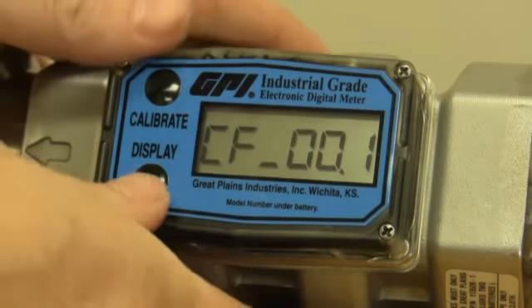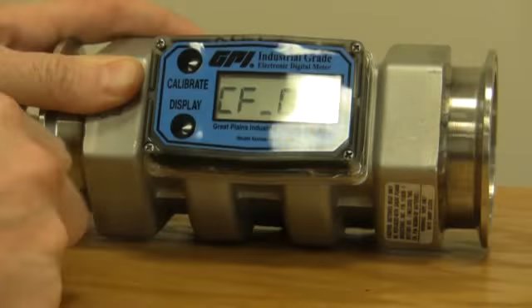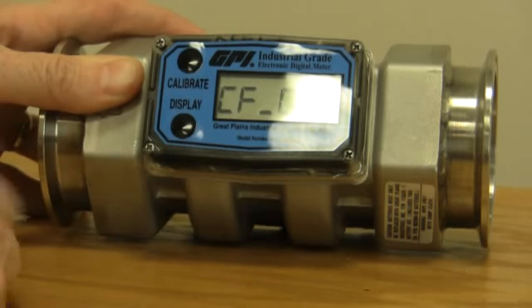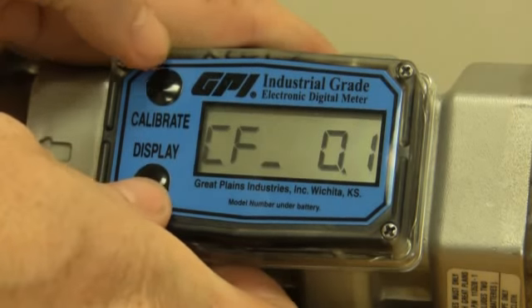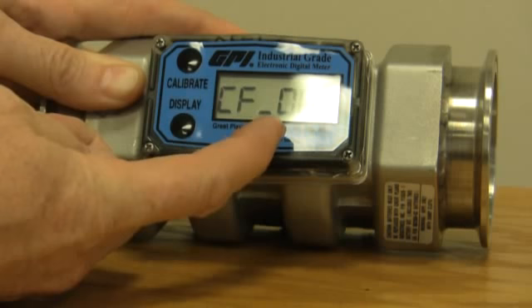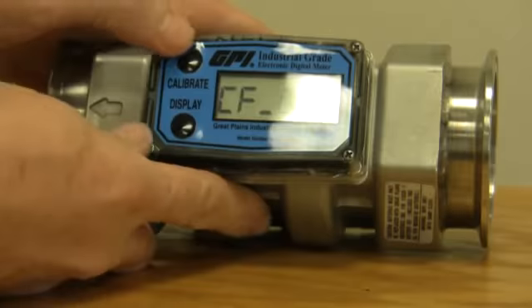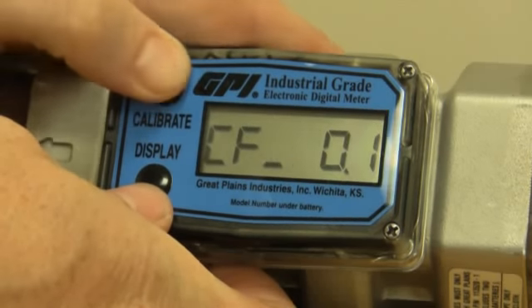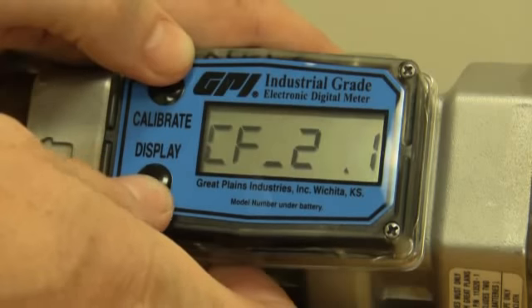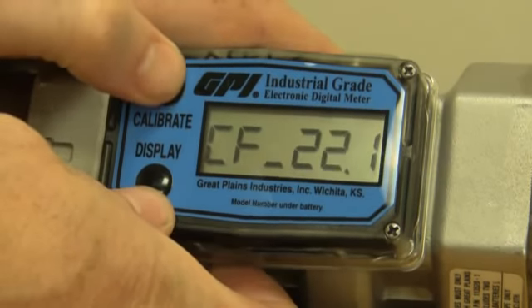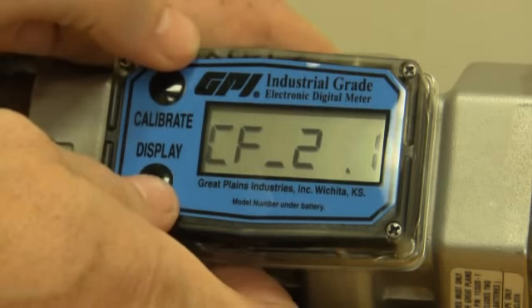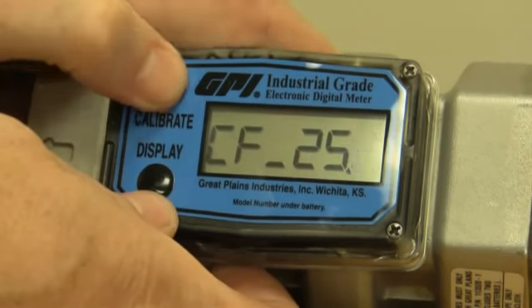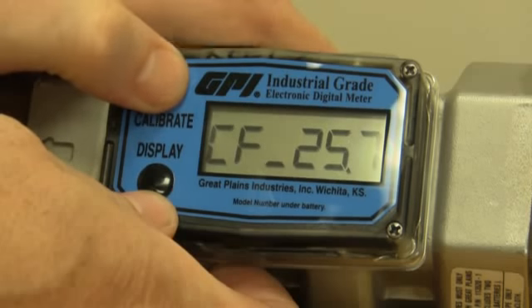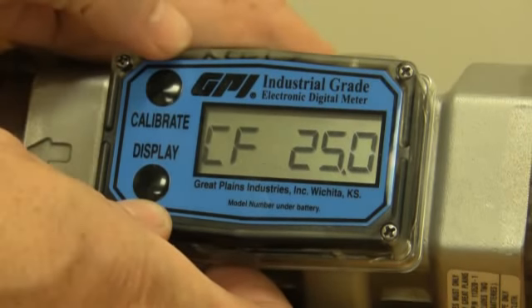You can see you've got this blinking line. That line lets you change that particular number. We don't want to change anything in this digit, so we're going to use the display button, push it one time, and scroll over to the next number. This one is 0. We want to change that to a 2. So if you hit the calibrate button 2 times, 1, 2, that's going to give you your 20. Hit the display button again, scroll over to the next number. We're going to make this a 5. That 1 right now just happened to be where it was. We're going to go all the way to 0. So 2, 3, 4, 5, and so on until we get back to 0.